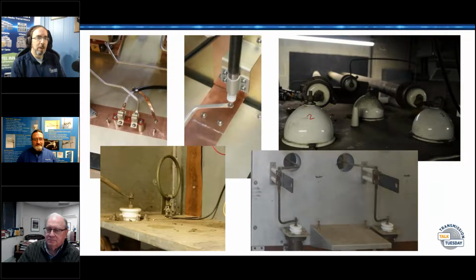And a 2 megawatt combiner, all these ceramic insulators on this top right picture with the bolts - all those bolts would be hemispherical and perfectly round, and they're tightened with something that looks like a glorified oil filter wrench, or they just pop on to cover the regular hex nut, either way. But the goal is not to have an exposed sharp edge.